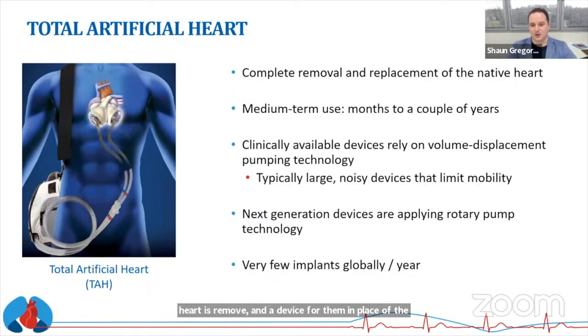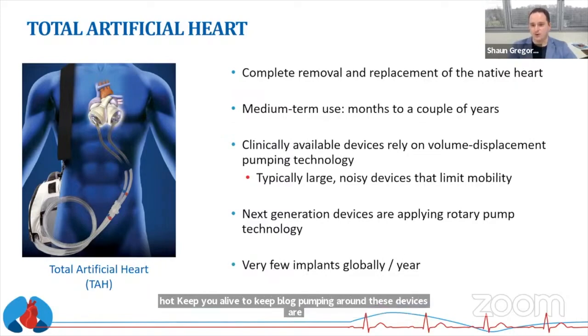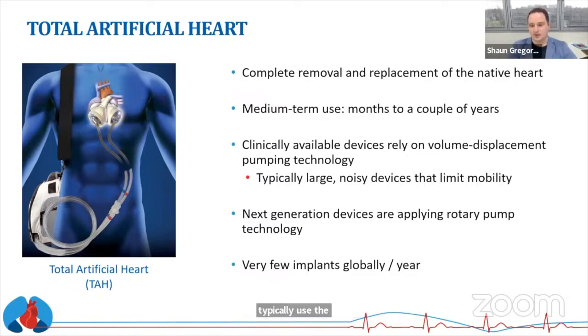These devices are typically used for medium-term use. They rely on technology that, if we look at the device in the image there, is essentially balloons within chambers. Those balloons are squeezed using compressed air from an air compressor outside the body, which pushes that compressed air in via those tubes into those chambers to squeeze those balloons to make it like a heartbeat. And if you imagine squeezing a balloon 80 times a minute for an entire year, that balloon's going to wear out pretty quick.